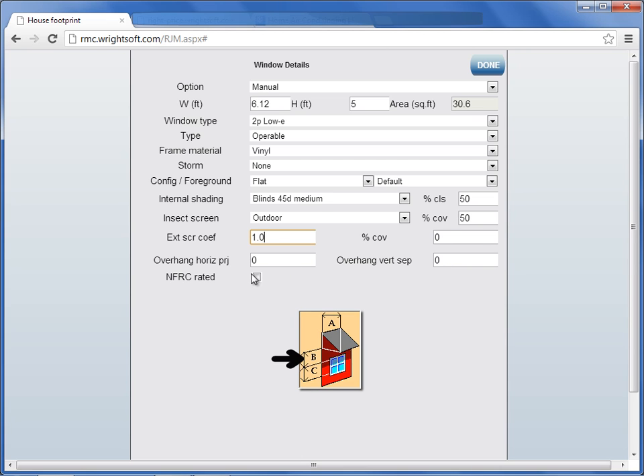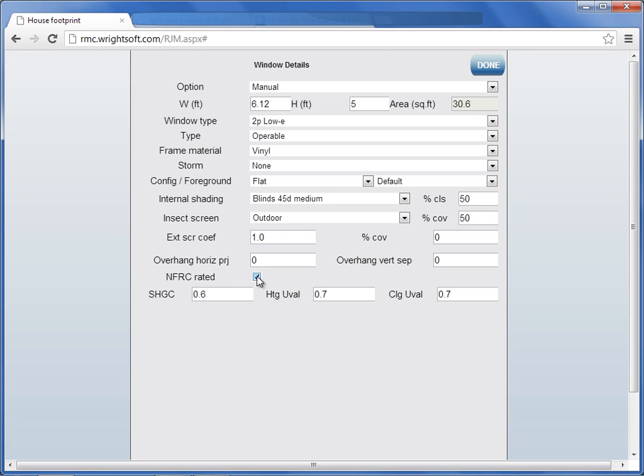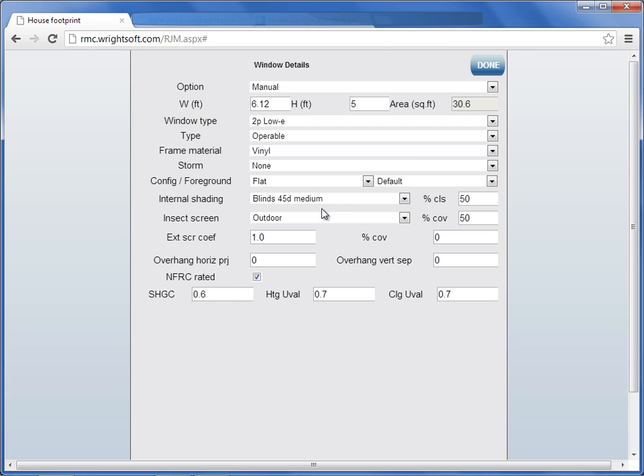The length of the edge from the face of the window, and the overhang vertical separation is the distance from the top of the window to the bottom of the overhang. The last row here is NFRC rated. This stands for National Fenestration Rating Council. You check this off when you know what the exact solar heat gain coefficient, and the exact U value is of a window. When you are done setting your window details, come up to the right and select done.